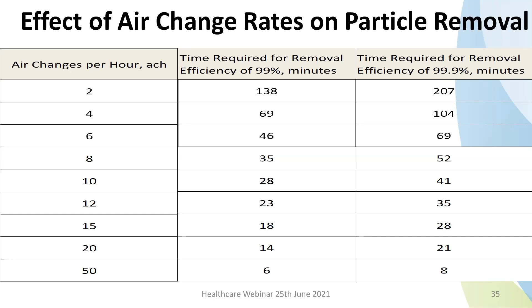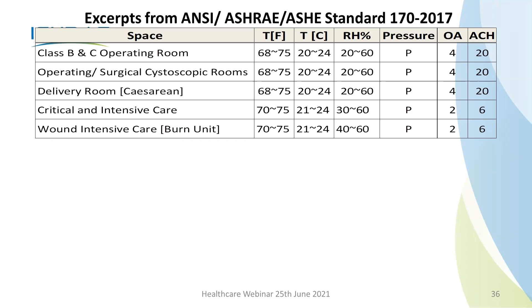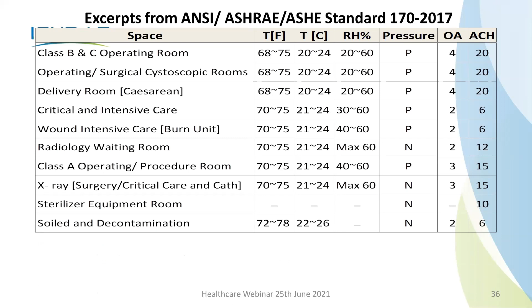Then for various areas in this standard, it mentions class B and C rooms. What are class B and C rooms? These are classified by whether the patient is being administered local anesthesia or full body anesthesia. If it is local anesthesia, it is class B. Full body anesthesia is class C. For operating rooms, surgical cystoscopic rooms, delivery rooms, for each and every room, you've got the recommended temperature, pressure, outside air, air changes, and recirculation. Similarly, if you go through this, there is no area that is not covered in that standard.